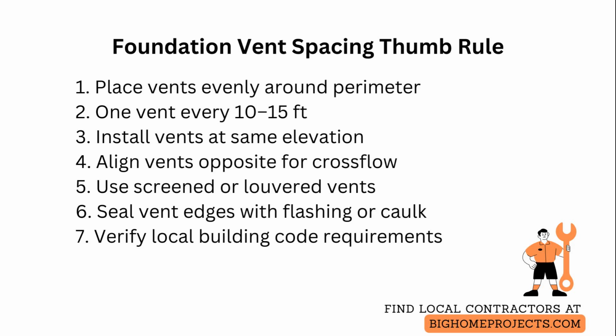Install vents at the same elevation around the perimeter and avoid grouping multiple vents on one side because that defeats crossflow and creates stagnant pockets. When possible, align vents opposite one another to encourage a breeze through the space.